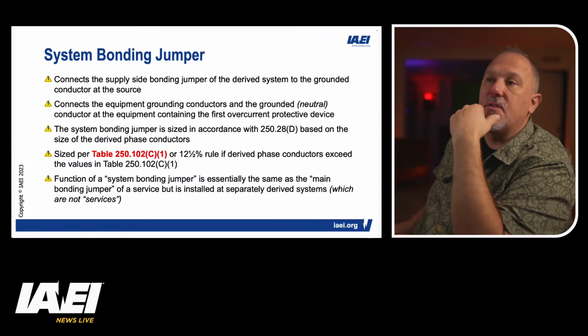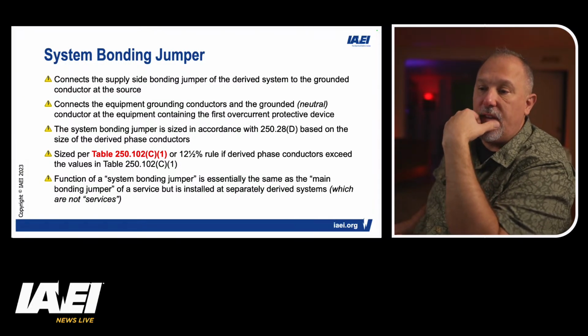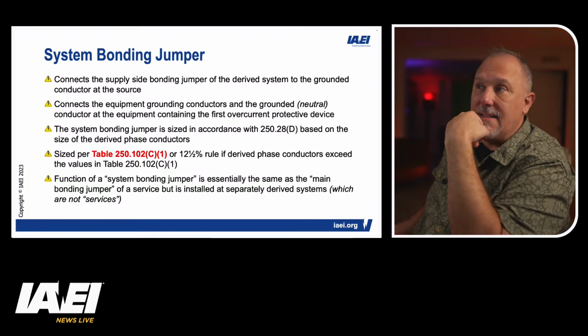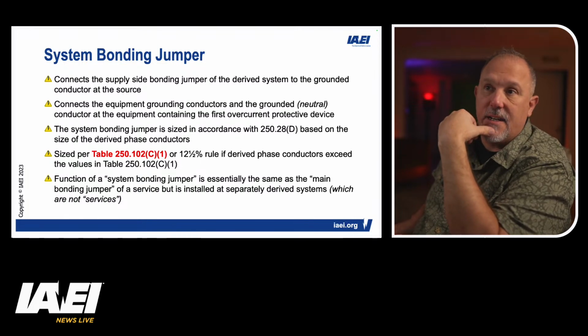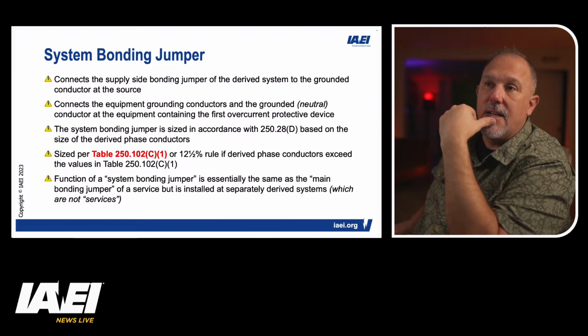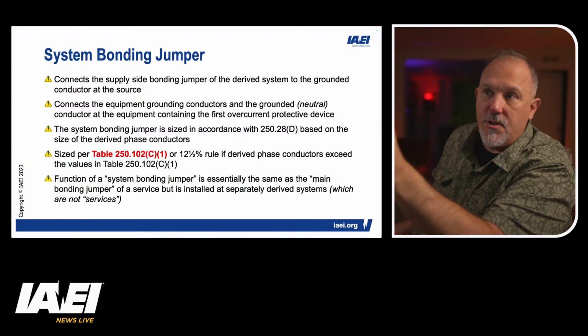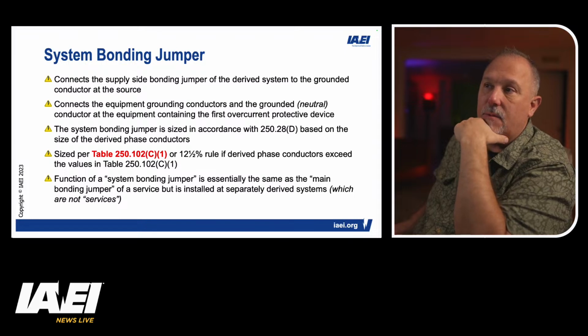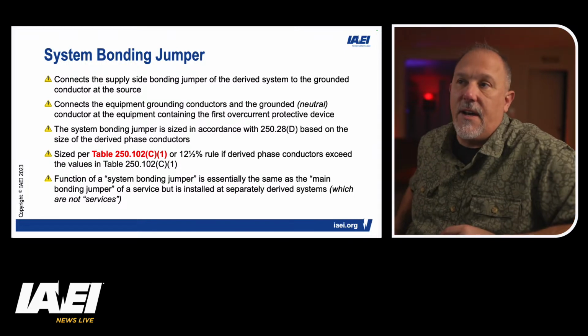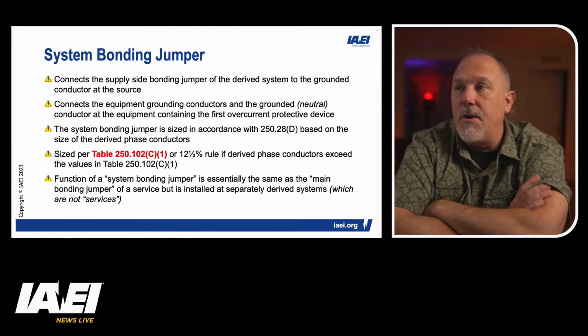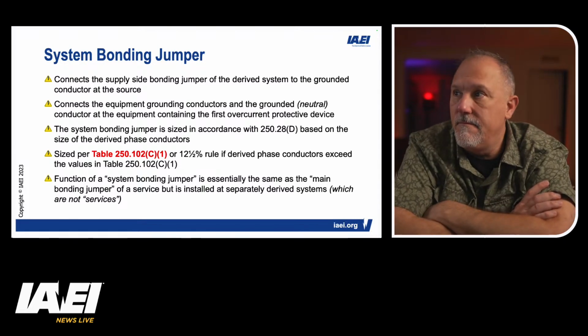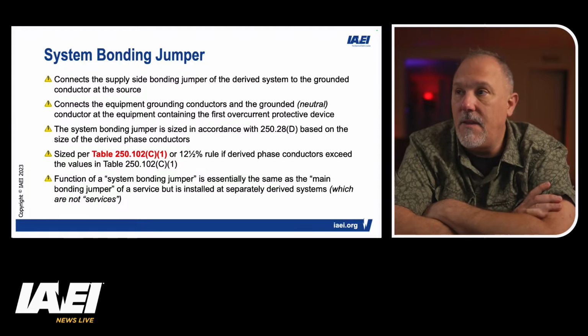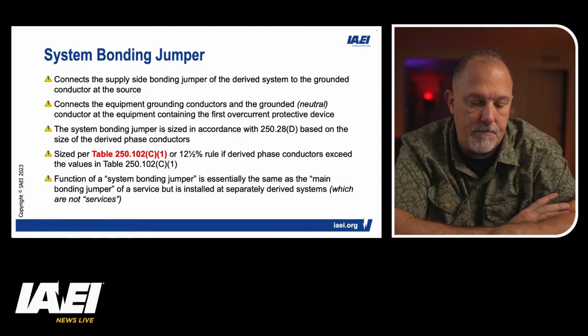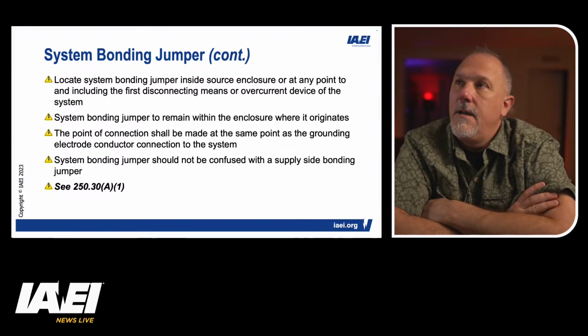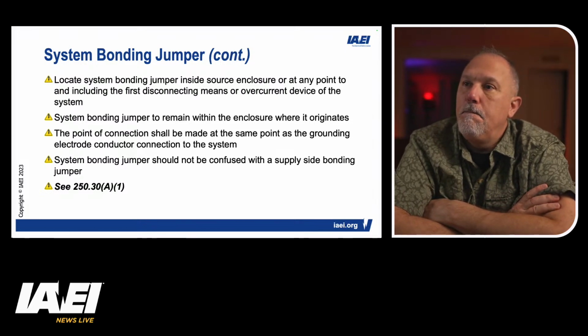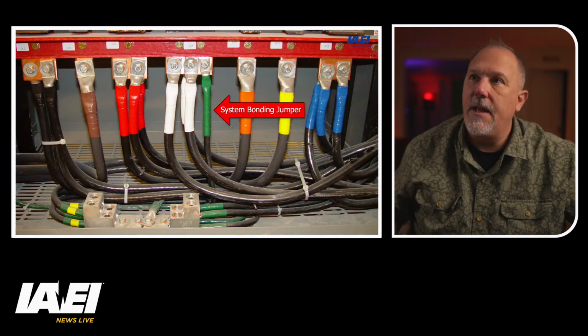The system bonding jumper size is in accordance with 250.28(D), based upon the size of the derived phase conductors, and 250.102(C)(1), or the 12.5% rule, if derived phase conductors exceed the values. The function of the system bonding jumper is the same as the main bonding jumper in these separately derived systems. So 250.30(A) is your reference.